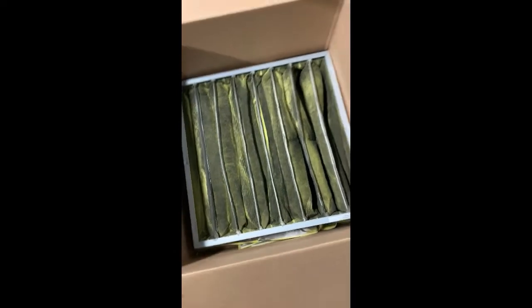My guys got the new filters in. This is the back of the final filters. We had to put clips, so it took them a good 20 minutes to put the clips and then install the new filters. Here are the conditions of the old filters — no mold, nothing. Last time we left them in for three years; this time it's just two. And here is the front of them.